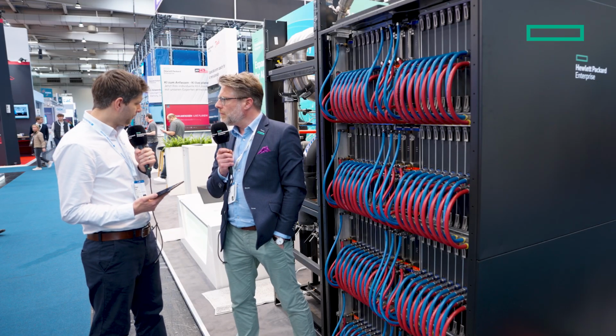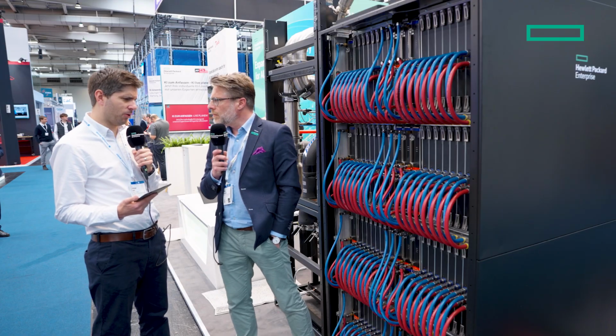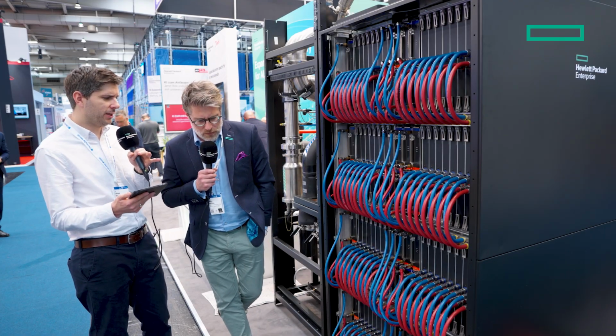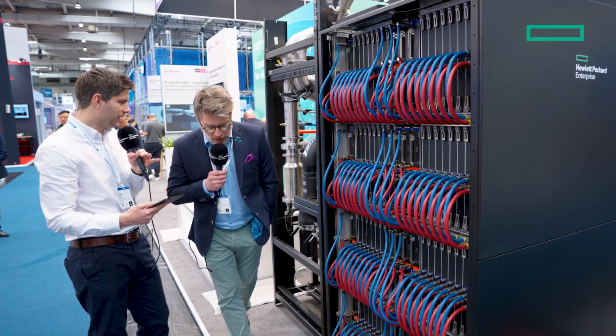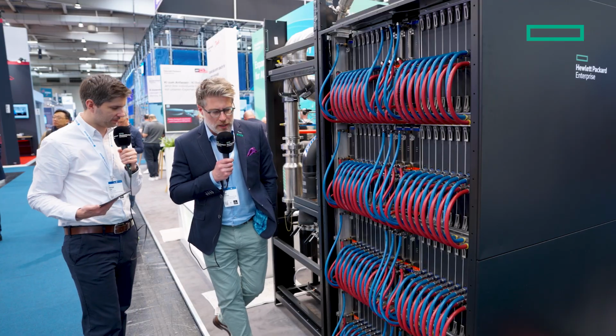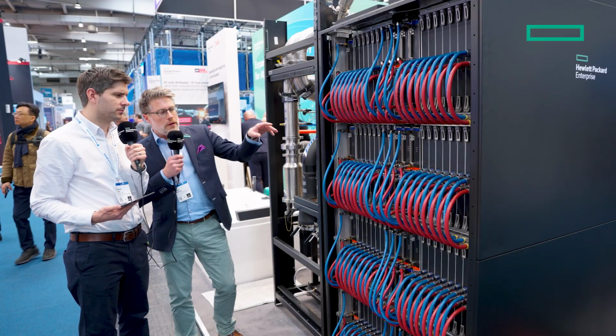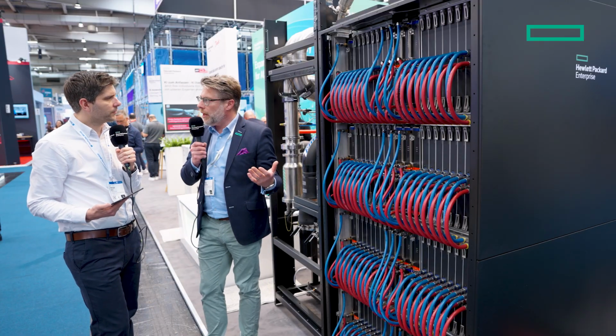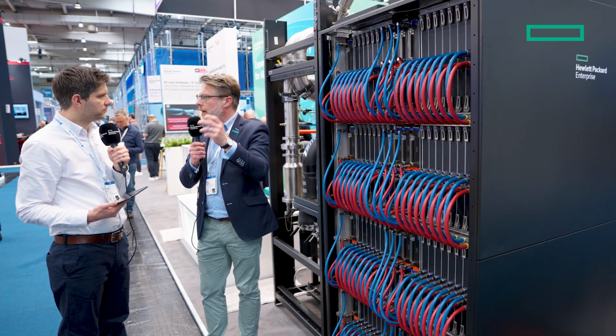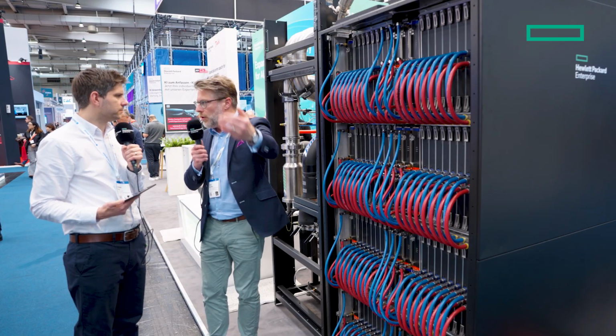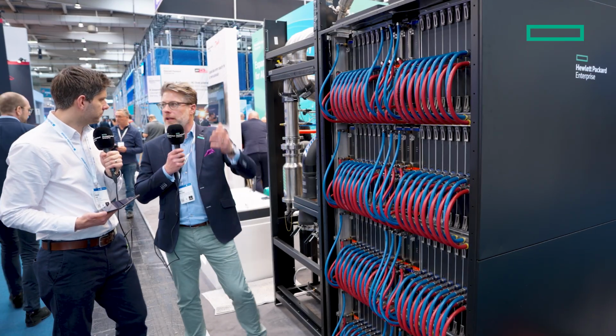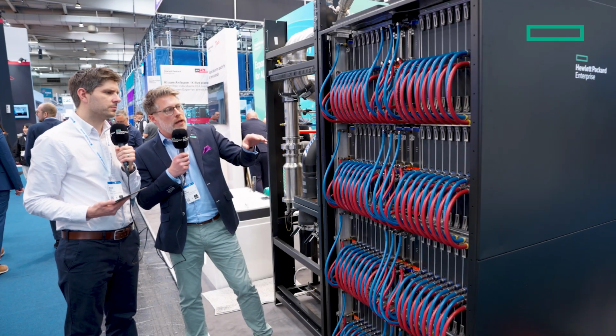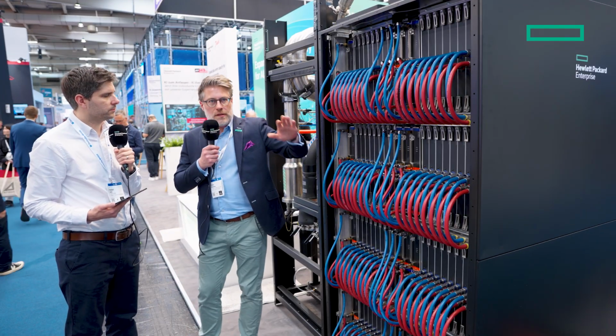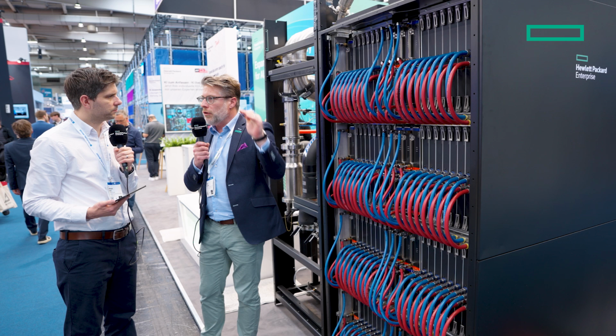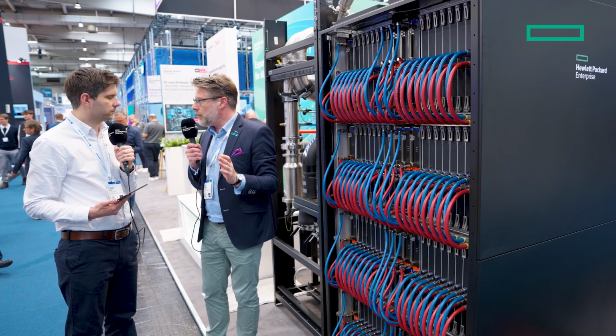Can you explain in more detail how the heat is transferred from this water cooling loop to actually do something with it? In that inner circle, we call it direct liquid cooling. It is water, but there is an additive in there, so it's not pure water—it's 75-80% water. That's circulating, and on these machines, the temperature level output is close to 50 degrees Celsius.